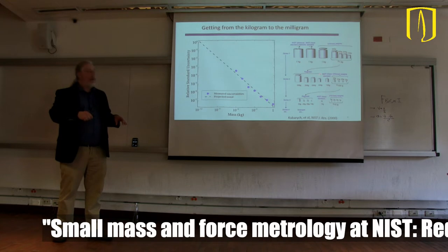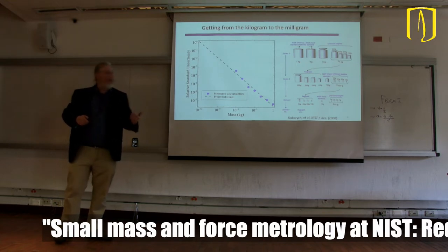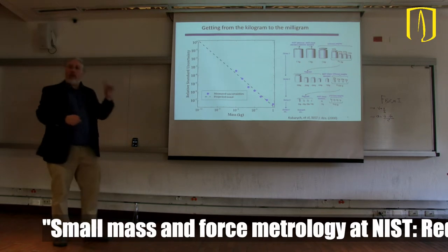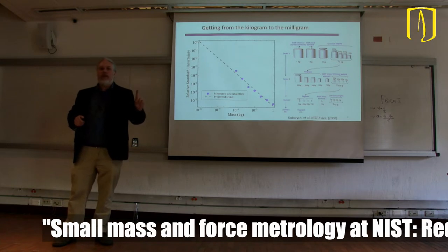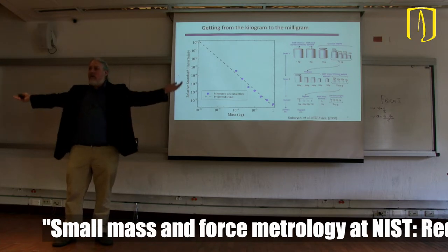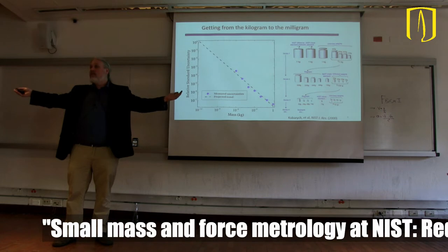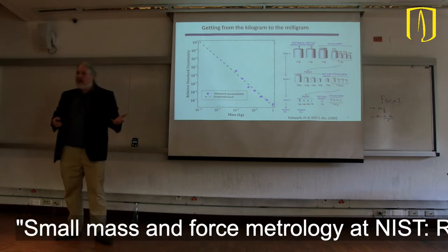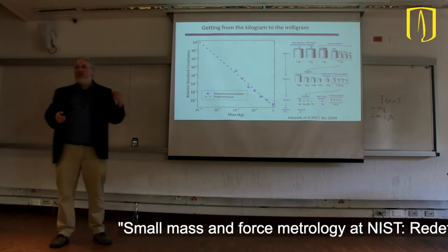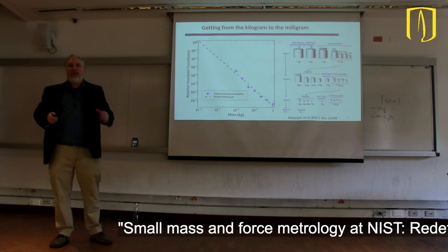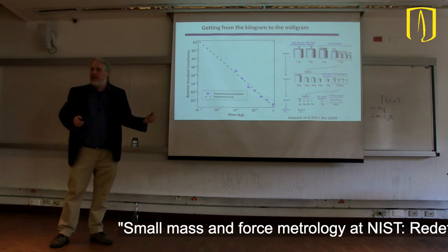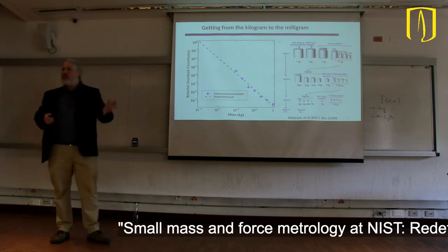100 grams down to 10 grams, and so on, and so on. But what happens is each time you do that, the uncertainty in the measurement increases. The balance is not perfect. The masses themselves can change slightly. You can have strange effects, like the phase of the moon can be important if you have that gravitational field, the water table, the density of the air if the humidity changes. All of these things contribute to uncertainty in the measurement.